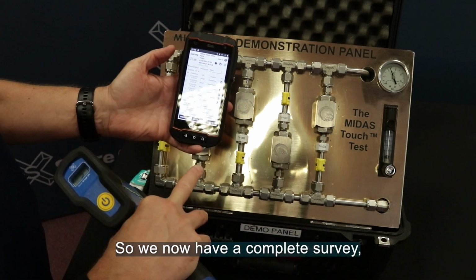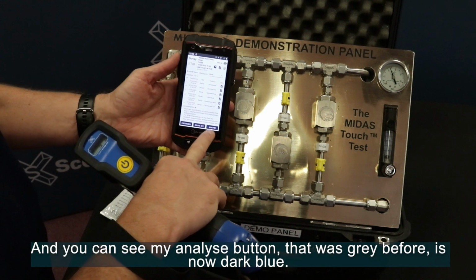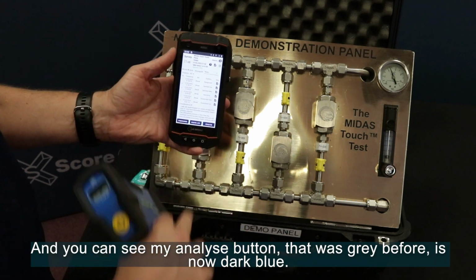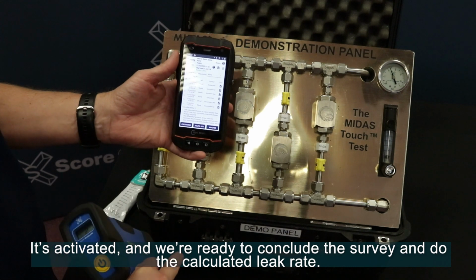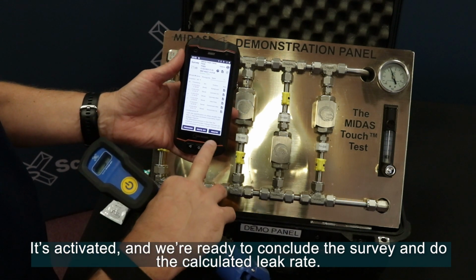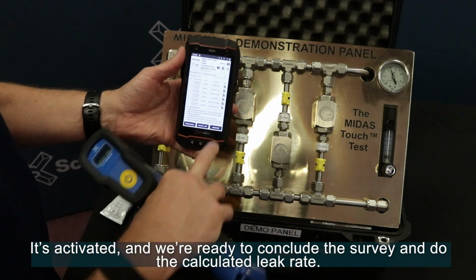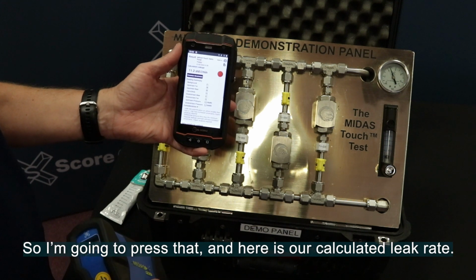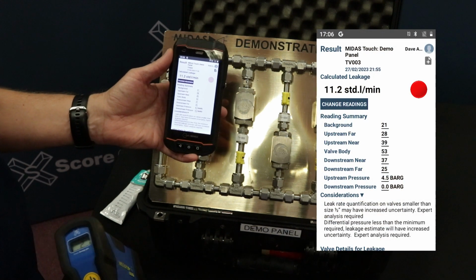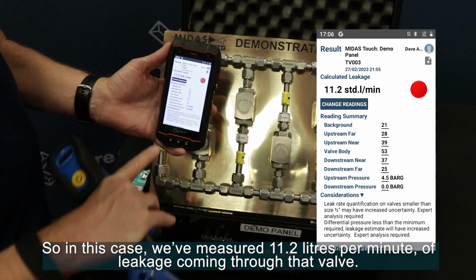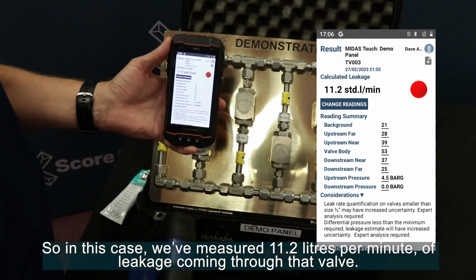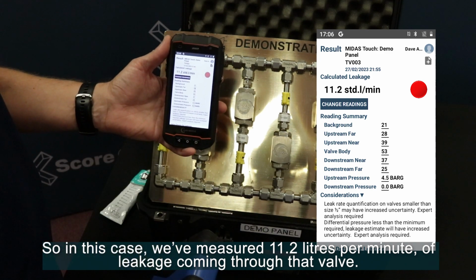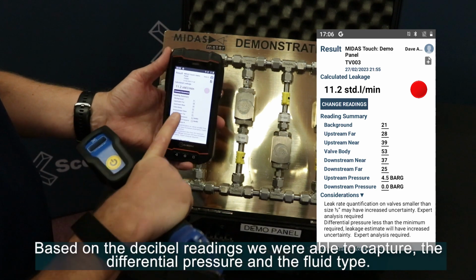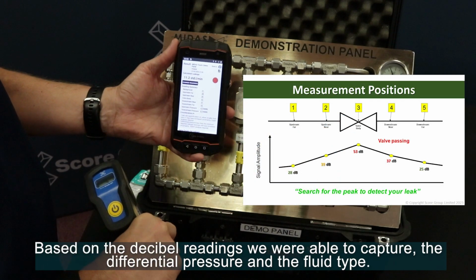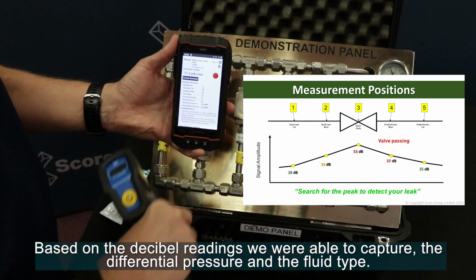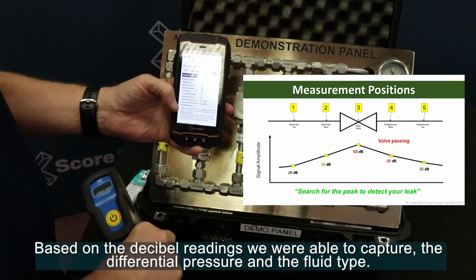So we now have a complete survey, and you can see that my analyze button, which was grey before, is now dark blue. It's activated, and we're ready to conclude the survey and do the calculated leak rate. So I'm going to press that, and here is our calculated leak rate. So in this case, we've measured 11.2 litres per minute of leakage coming through that valve based on the decibel readings that we were able to capture, the differential pressure, and the fluid type.